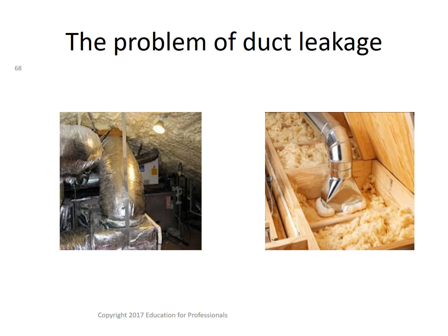So locating ducts in conditioned space eliminates many problems with leakage. They're often installed in chases, which can be problematic, and framed air passageways situated behind ceilings or wall finish have basically the same problems. These chases are often connected more directly to unconditioned space rather than interior space, and so you have a mixing of two different types of air, when it should be indoor air quality for the interior space. So it is important to seal these areas completely from unconditioned spaces. And a common practice is sometimes putting the air handling unit in the garage.